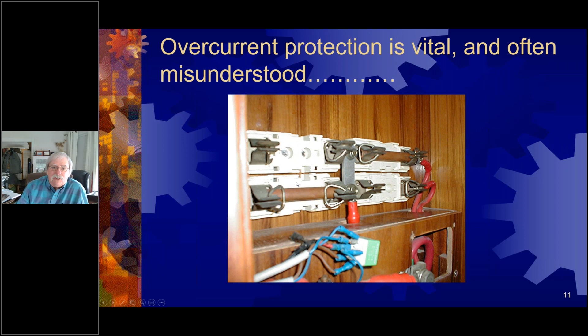The rules, we talk about this a lot in all of our courseware. The 7-40-72-inch rule, as I describe it, and basically this is the location for overcurrent protection devices, and these are maximum numbers. The basic rule says 7 inches from the point at which the cable is connected to a source of power. That might work fine on the back of a panel board. You can achieve that pretty easily, but the 40-inch rule comes into play if you're connecting to a source of power other than a battery post.